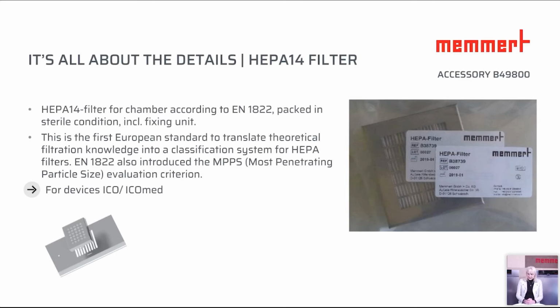Now we are in the range of the CO2 incubators. The CO2 incubators can be equipped with a HEPA filter, that is for the interior filtration. HEPA filter 14, according to EN 1822, which is packed in a sterile condition, including a fixing unit, is a high efficiency particulate air filter, and theoretically it can remove at least 99.97% of dust, pollen, mold, bacteria, and airborne particles with a size of 0.3 microns.